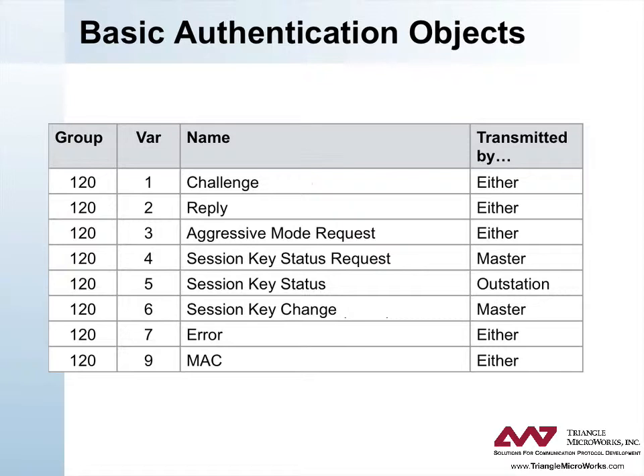There are two types of keys used in DNP3 secure authentication: the pre-shared key, known as the update key, and a session key in each direction. The update key is used to periodically change the session key using the three session key messages. An optional error message can be used for debugging a secure system to determine why authentication is failing.